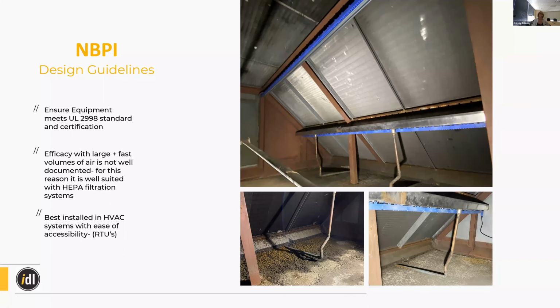So there's this standard, the UL 2998 standard and certification. If you are going to explore needlepoint bipolar ionization, you just want to make sure that it meets this standard, because there is a potential for ozone generation, which is also a lot of people's reservations about this technology. Like I said, the efficacy with large and fast volumes of air is not well documented. And it's best installed in a place with ease of accessibility, like rooftop units, where you can access it a lot and make sure it's working. But the big one is, again, that ozone generation.